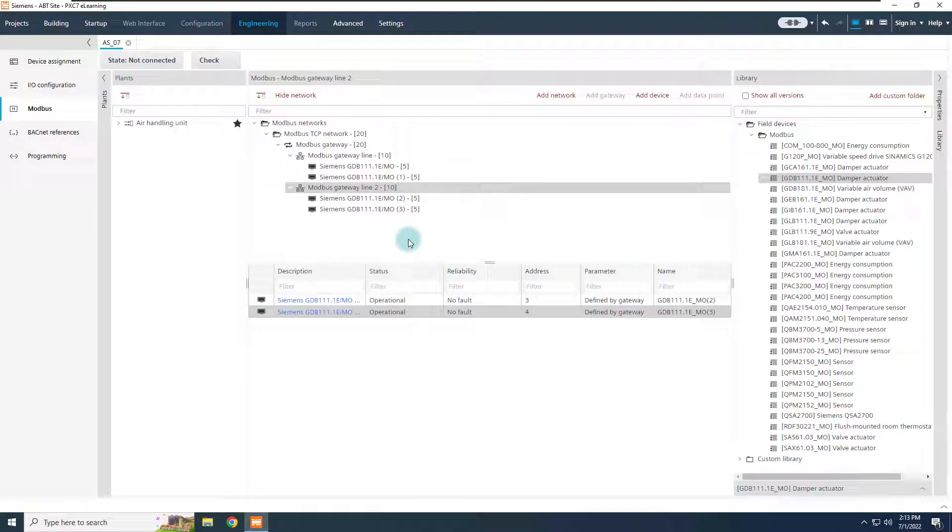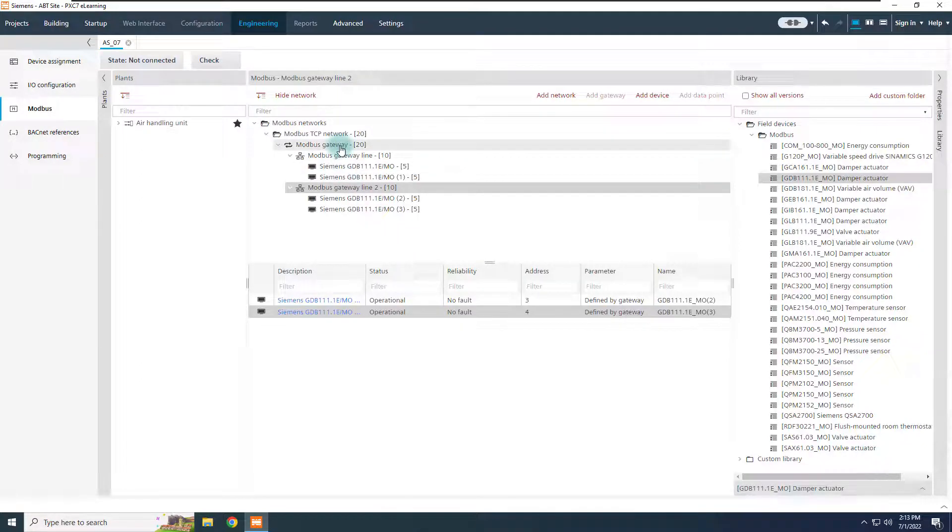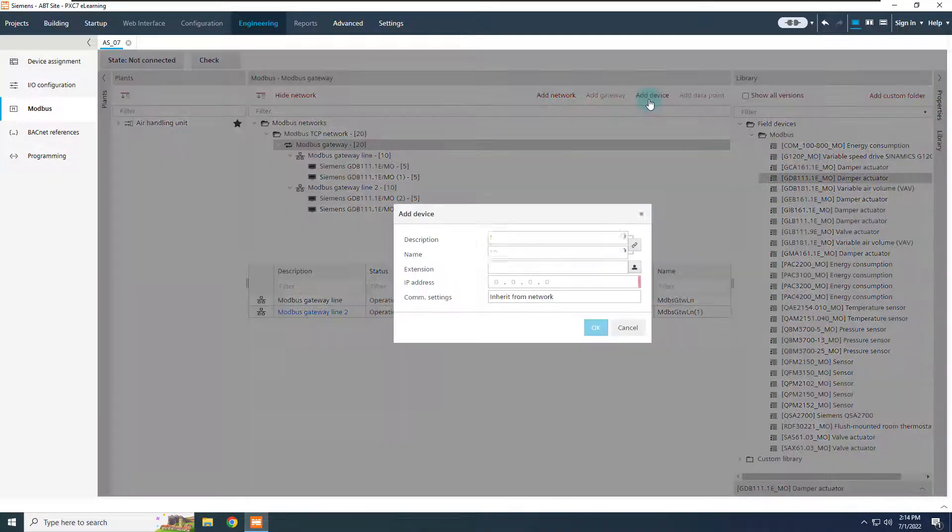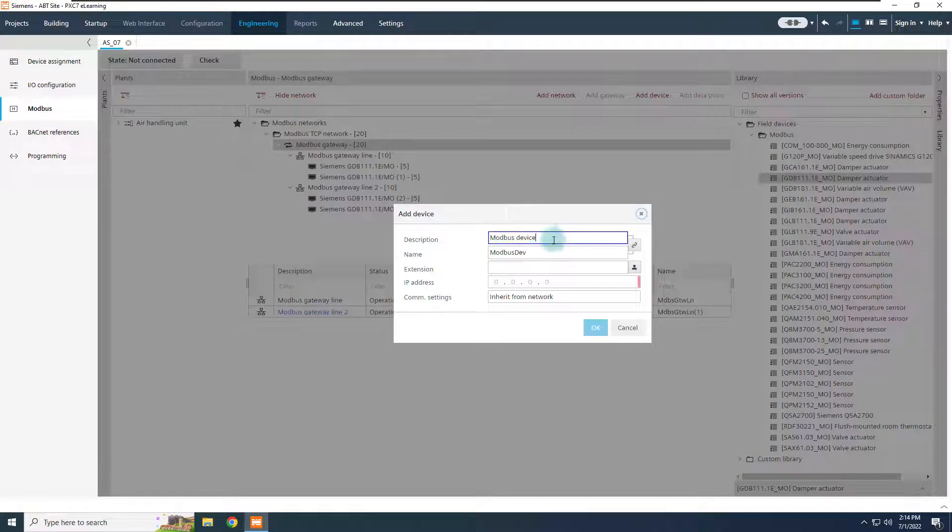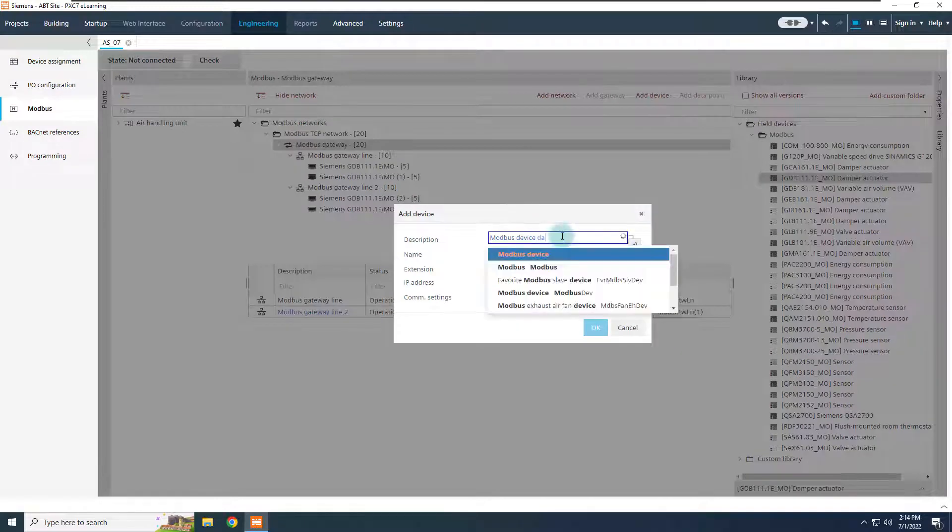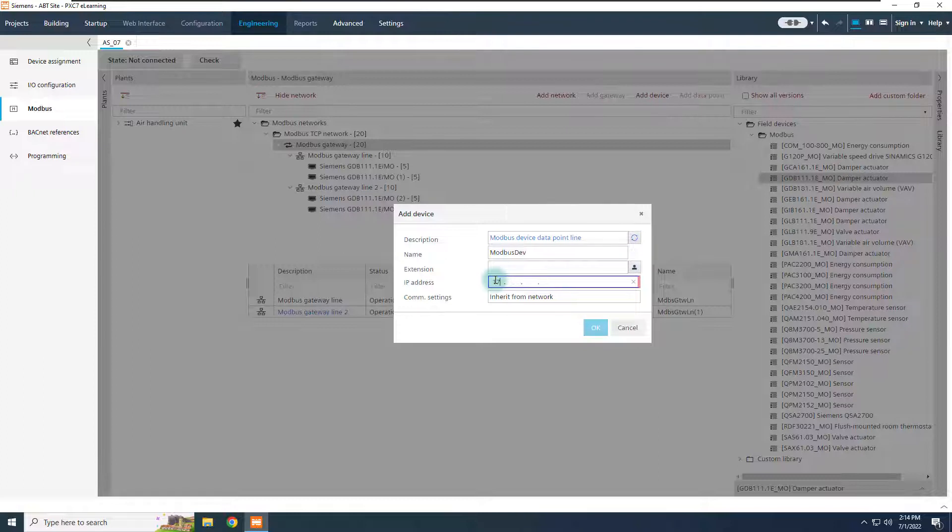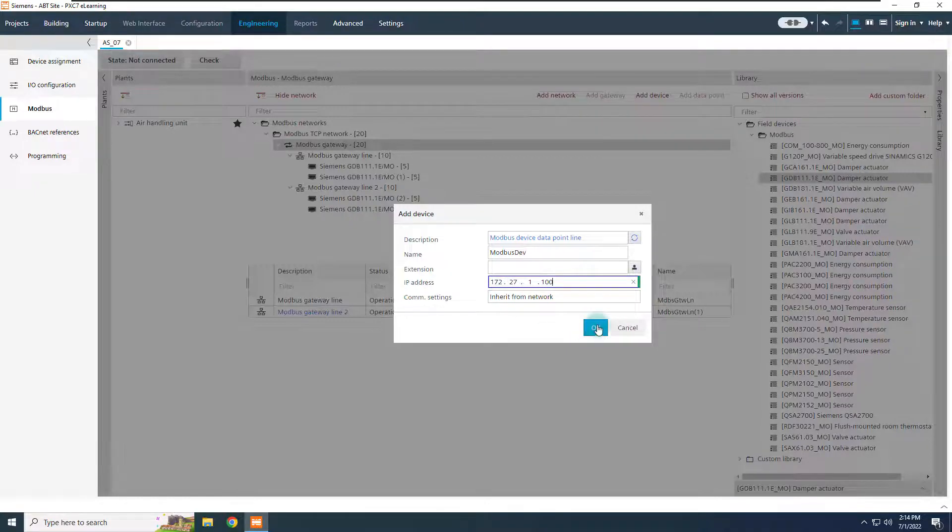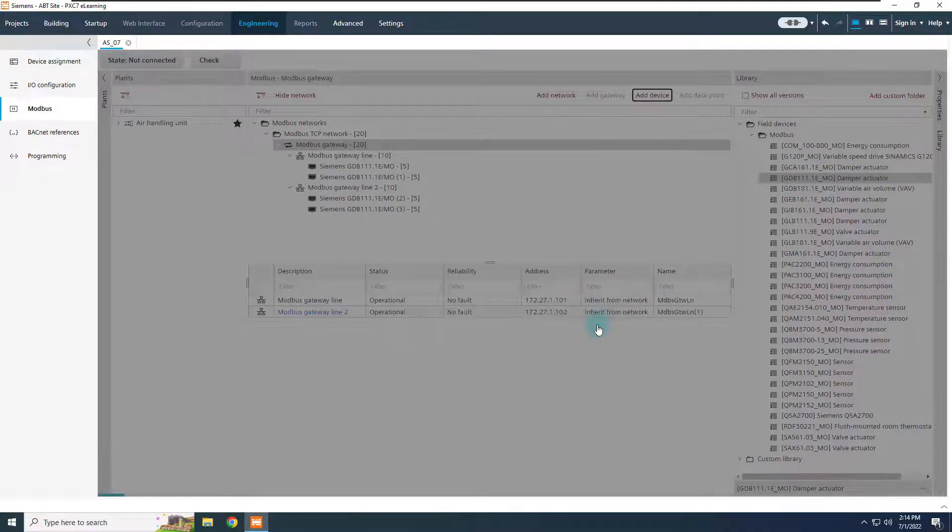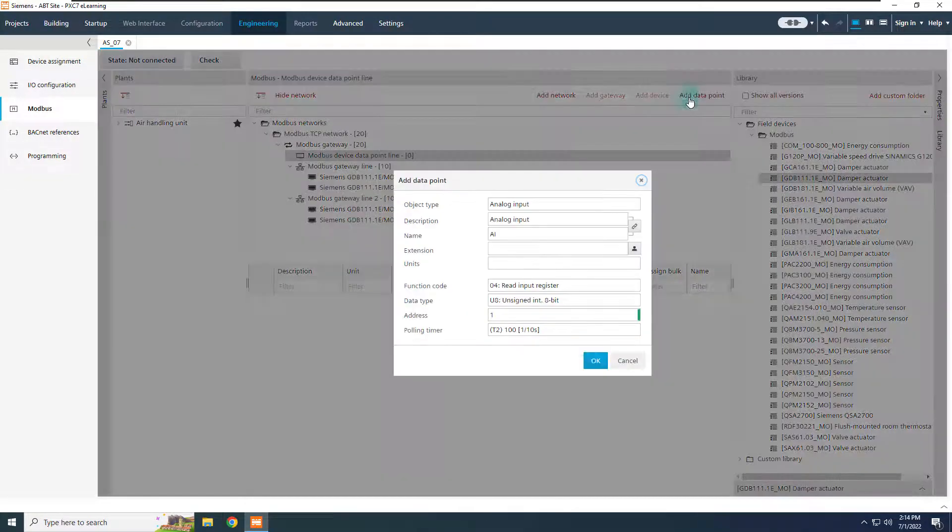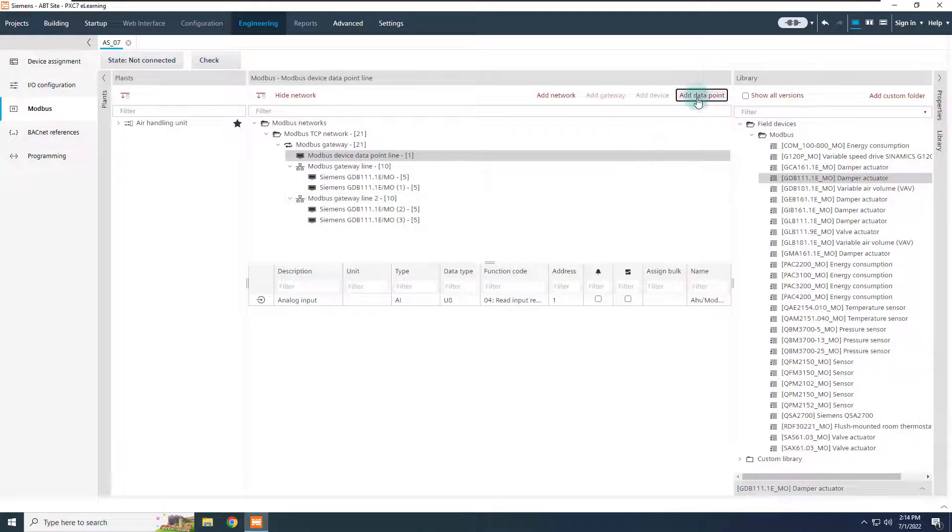If the gateway itself carries data points, add a TCP device from the gateway node. Give a meaningful description, if required, and indicate the IP address of the gateway, which is, in our example, 172.27.1.100. Add now the data points, following the same workflow of a typical Modbus server.